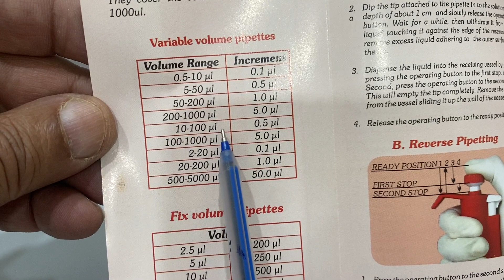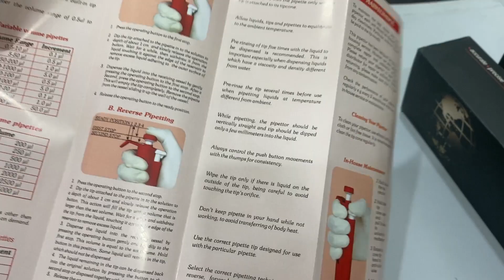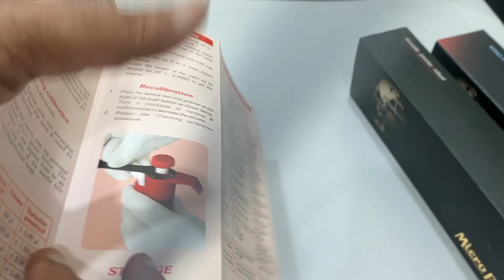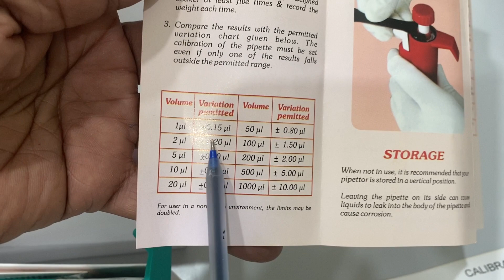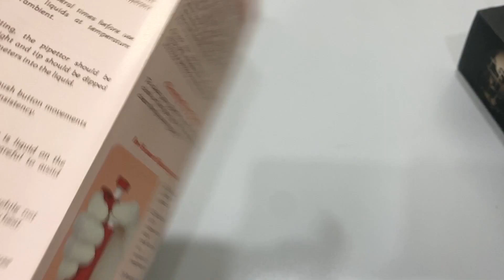And there are fixed volume pipettes also, almost the same as the pipettes available. And we have got the multi-channel, 8-channel and 4-channel pipettes. So here it tells you first step, second step, push it, make it ready, and how to use it. The manual shows the parts. These are the working. These are the calibrations. What are the variations allowed in that particular calibration? How to change it? Checking calibration, recalibration, all these. And you just see, these are the problems. It tells you the problems and what the solution is. Slowly it gives you, and a full manual is provided regularly.